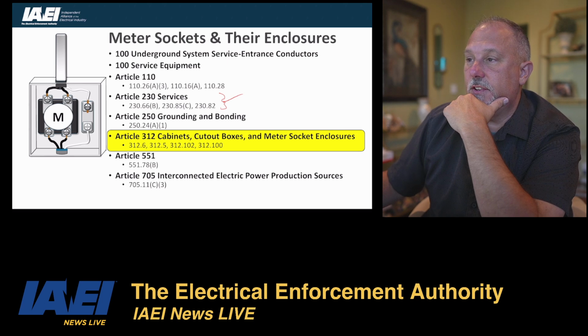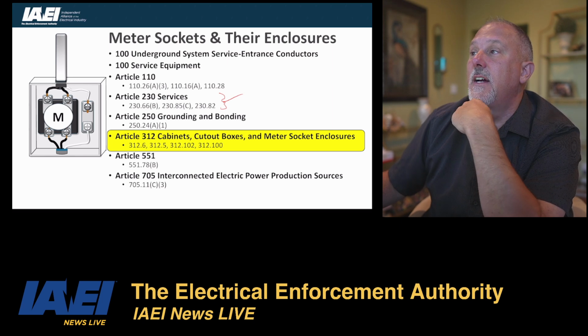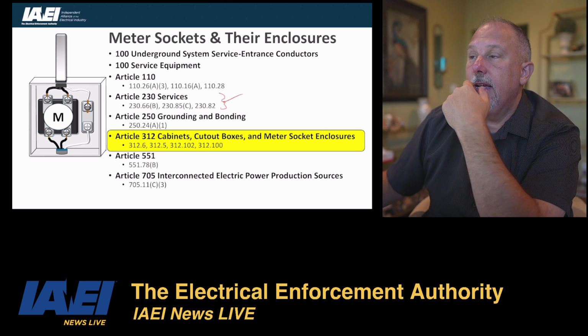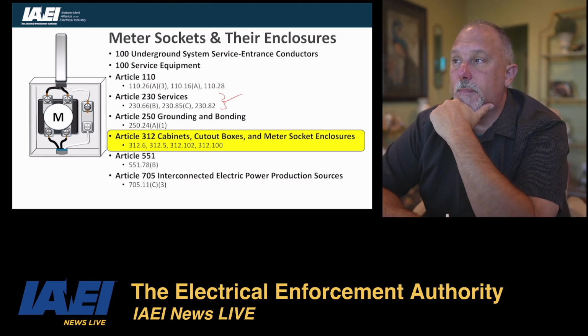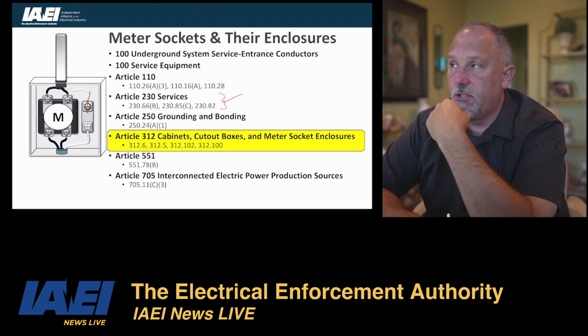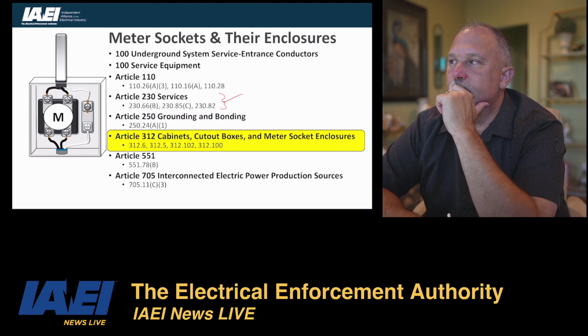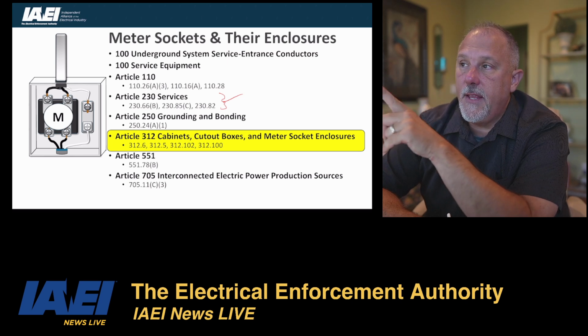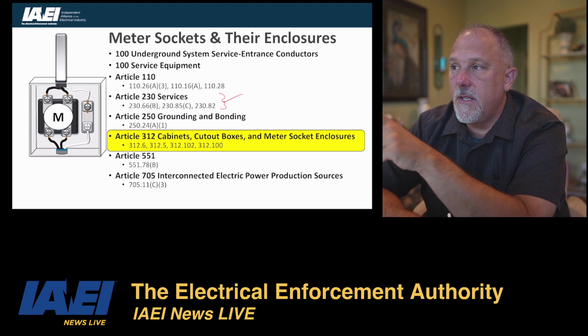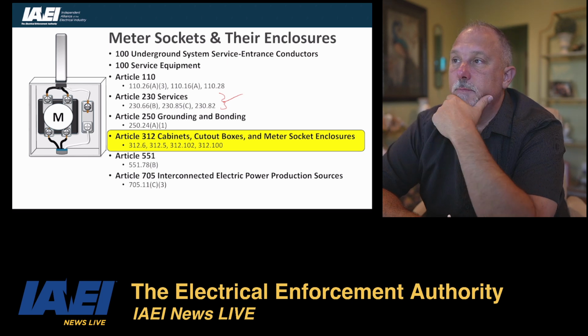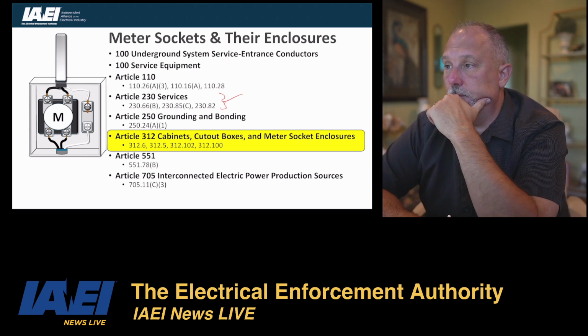230.85 and 82. So let's take a look at 230.82. 230.82 says this is equipment connected to the supply side of the service disconnect. And item number 2 on the list is meters and meter sockets, if all metal housings and service enclosures are grounded in accordance with Article 250, Part 7, and bonded in accordance with Article 250, Part 5. And the meter disconnect. Now, the meter disconnect is separate from the meter. So the meter socket is mentioned in 230.82, item 2.